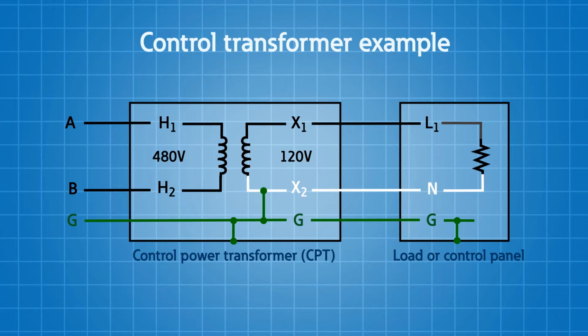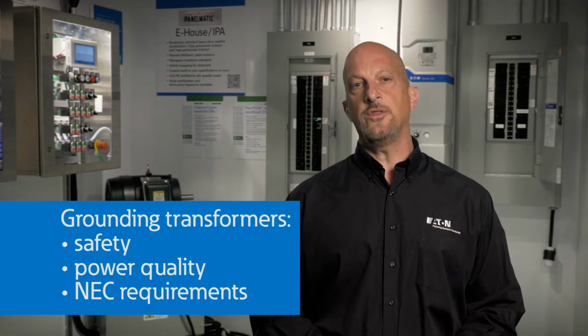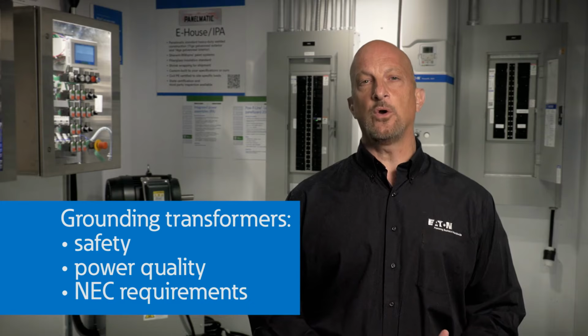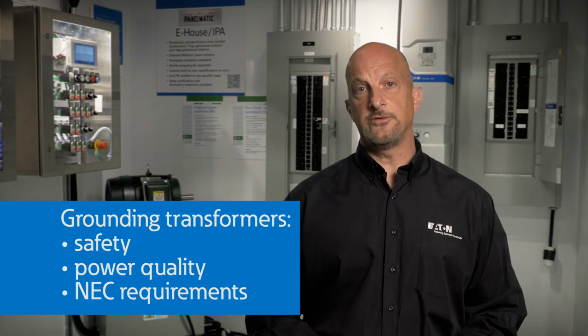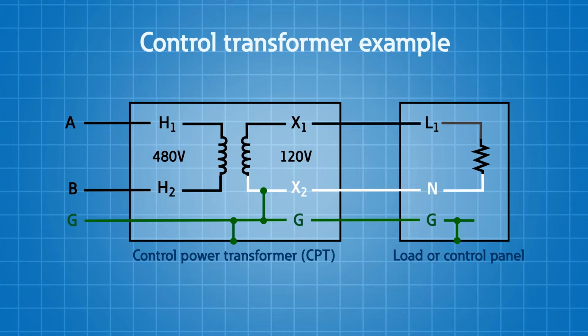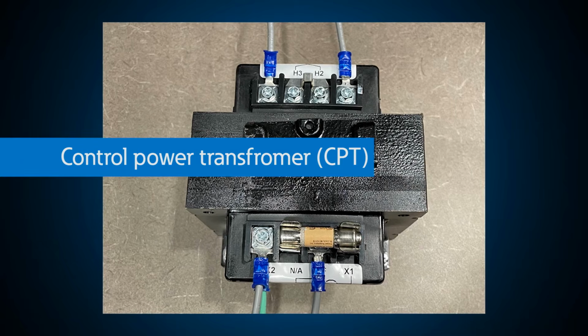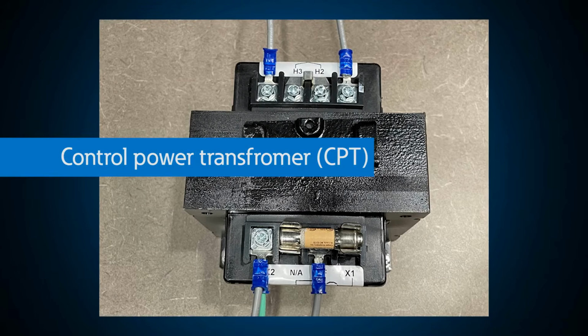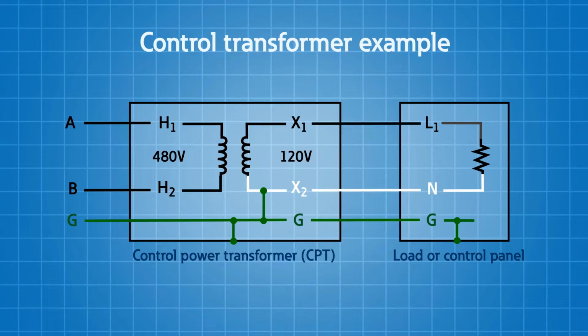This would allow you to establish a reference to a known reference on the secondary of the transformer when this is required for safety, power quality, or by NEC requirements. X2 is also considered the neutral conductor for typical low voltage applications and would only be grounded at the transformer and at no other point downstream on the circuit fed from the transformer. For this situation, a simple wire connecting X2 to the incoming ground wire coming from the primary of the transformer would suffice for a control power transformer.